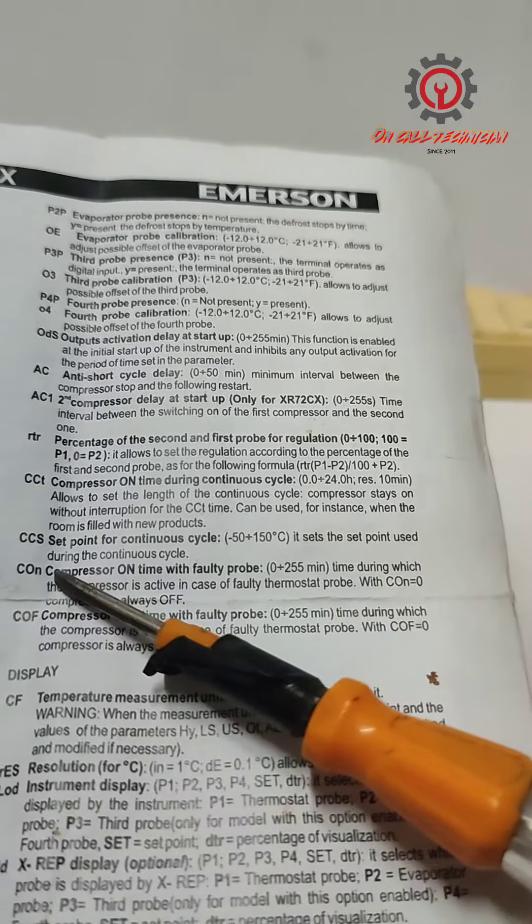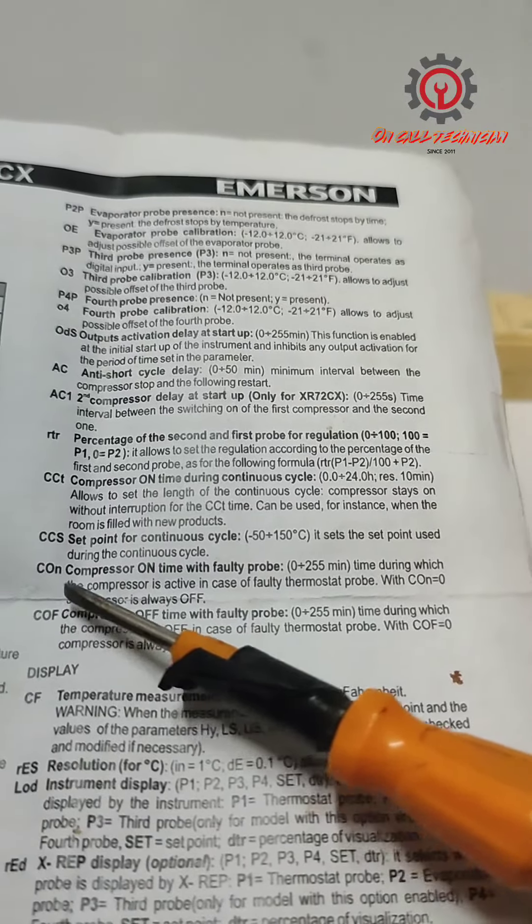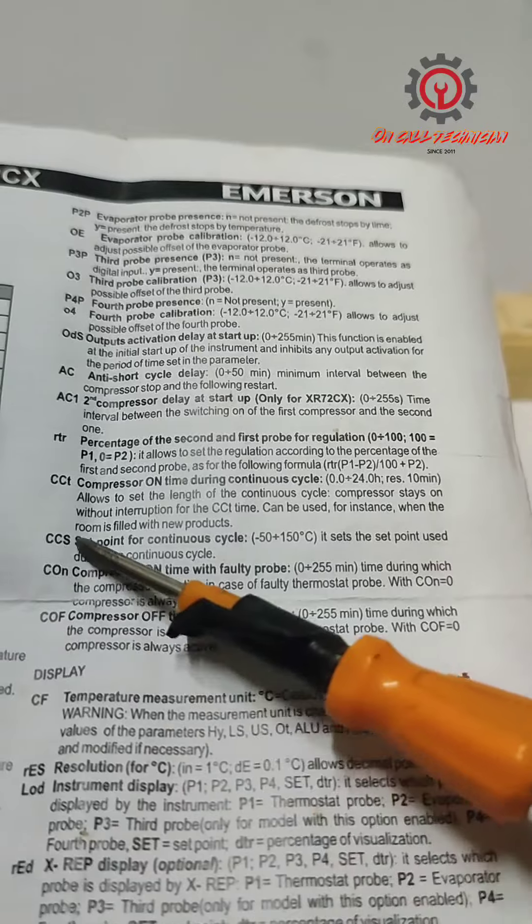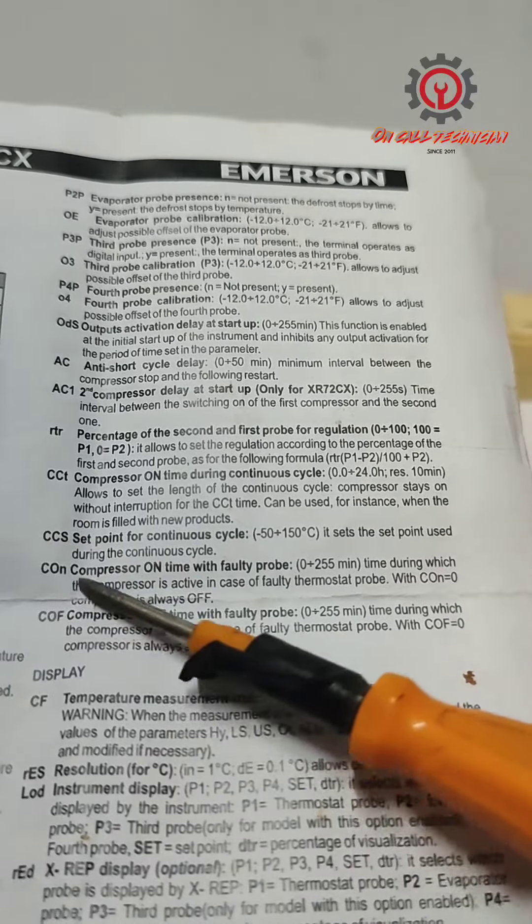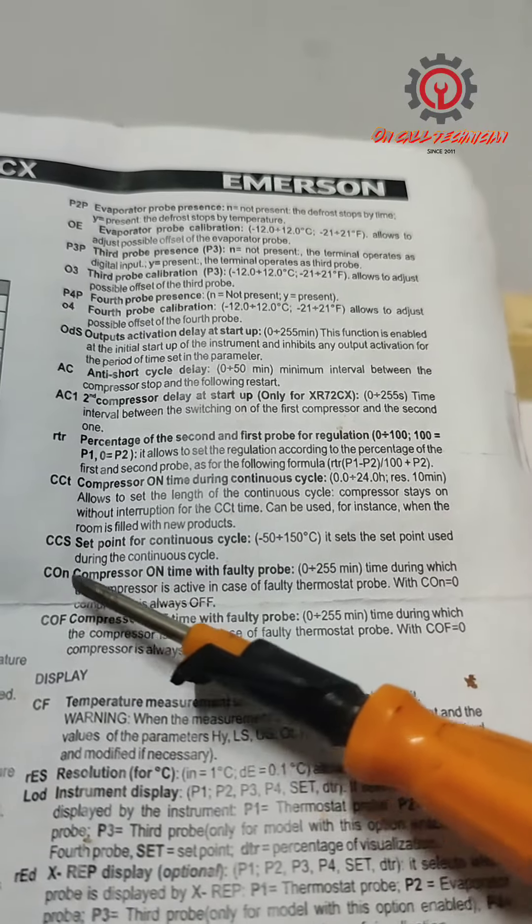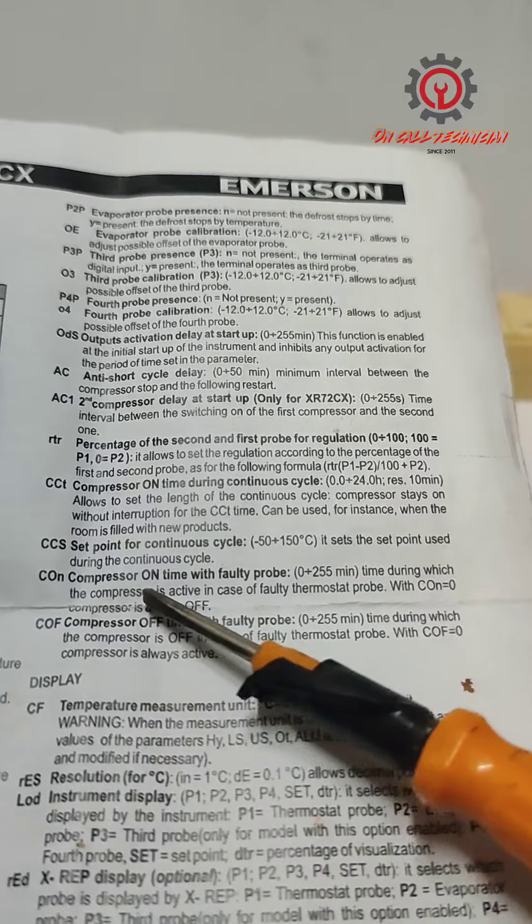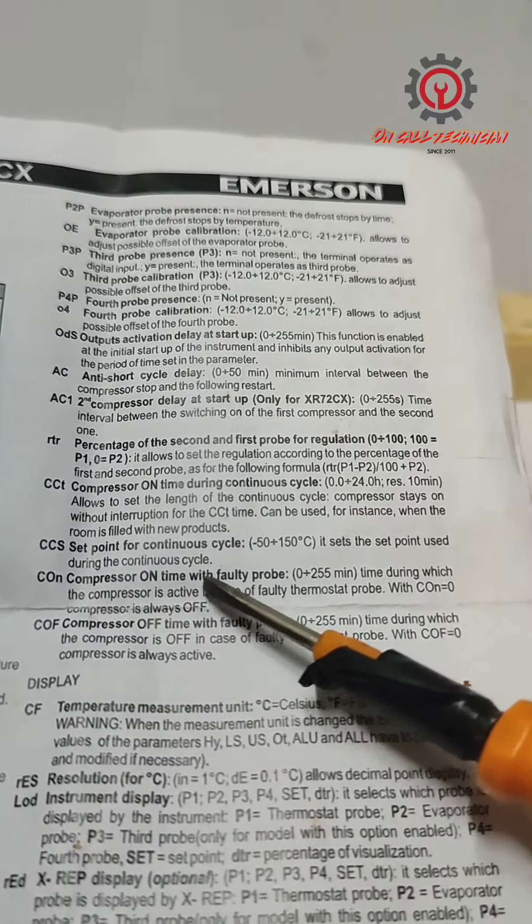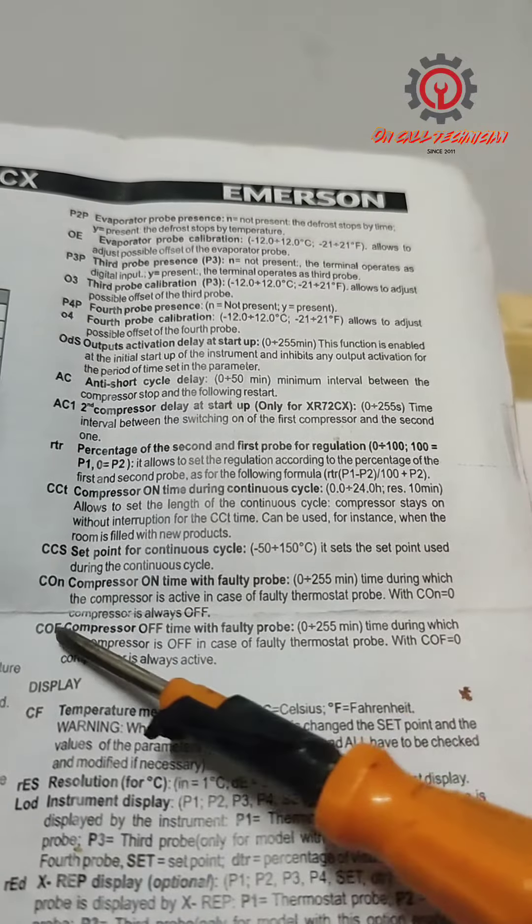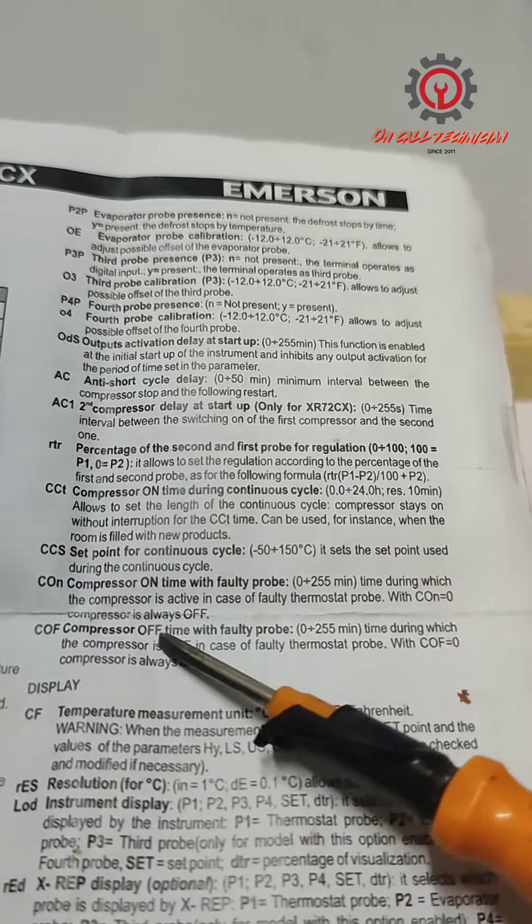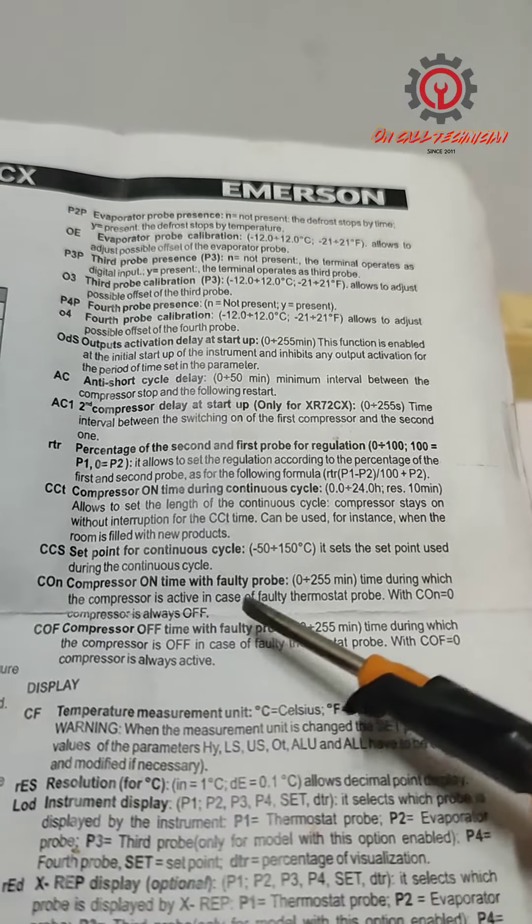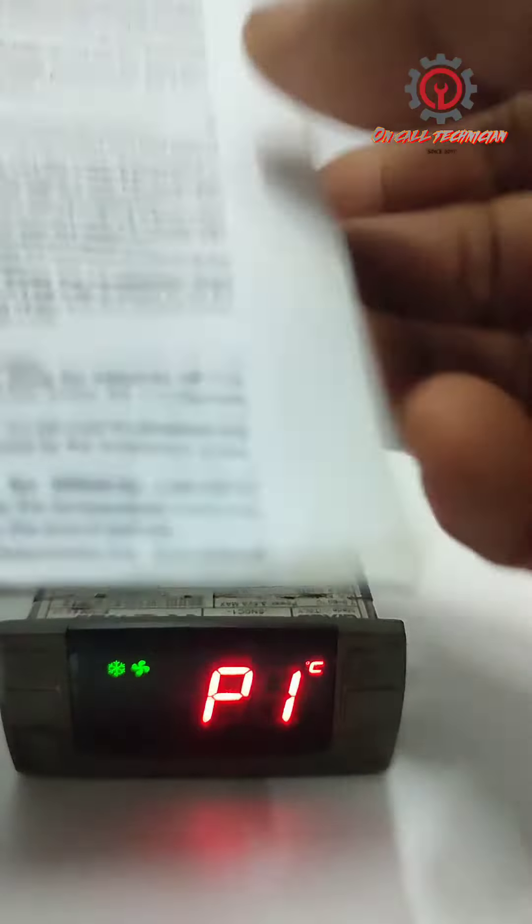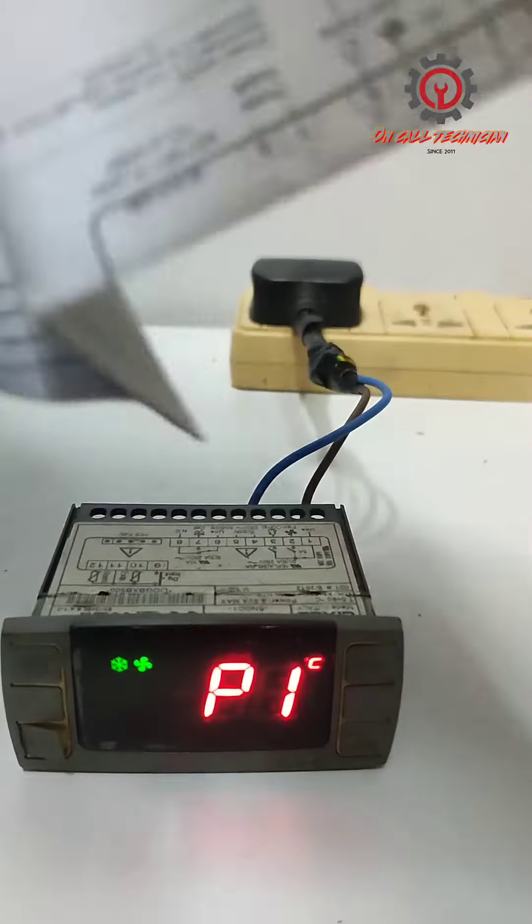C on and C off. These two parameters manage the control. C on is compressor on time with faulty probe, and C off is compressor off time with faulty probe. If you're going to program this, make sure that the unit is in line with your chiller or freezer.